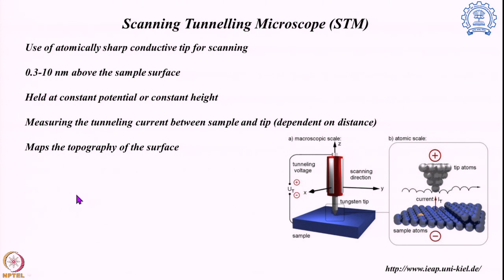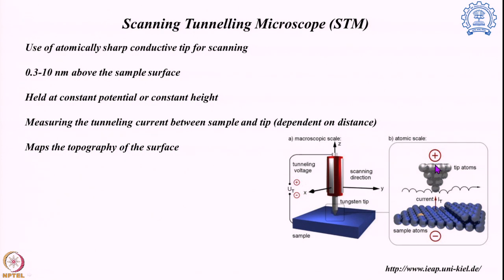Then come the scanning probe microscopes. Unlike the previous electron microscopes where we bombard the system with electrons, in the probing systems we use a sharp tip which can be handled at the atomic scale, and that is used for scanning. The instrument shown here has a tip with only a few atoms present, and that is a conductive tip capable of transporting electrons, so we can control its potential and the electricity passing through it.